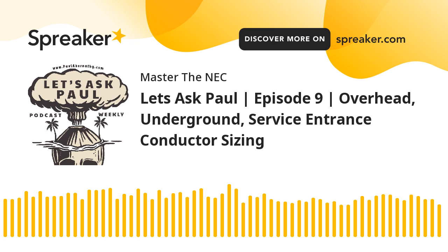And that is underground service conductors, overhead service conductors, and of course, the transition from the service point or the point of attachment on the building, what runs down the side of your building, say down to your meter, they would be service entrance conductors. Okay. So understanding the nuances, if I had a pole on my property and the utility stopped at the pole, and then I controlled the overhead conductors that go down to the side of my building, which can happen on large rural properties, then those would be overhead service conductors. And then once they got to the point of attachment of the building, they would change over to service entrance conductors.